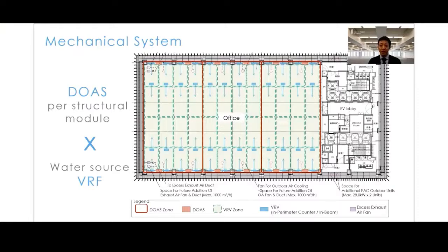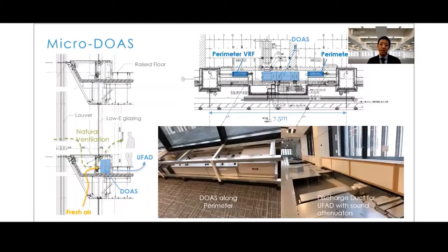For the mechanical system, as part of the integrated active components, the office floors are equipped with DOAS with water source VRF, which are zoned in small areas within each floor. In this way, the system can conform with various diverse work styles while minimizing the energy used for the tenants. Micro-DOAS, a very small dedicated outdoor air system supplying only 650 CMH, was developed and integrated with the facade. It consists of high-efficiency EC fans and is located between the columns at the north and south perimeter. The control is designed to automatically optimize the ventilation mode among demand control, airside economizer, and natural ventilation hybrid mode.